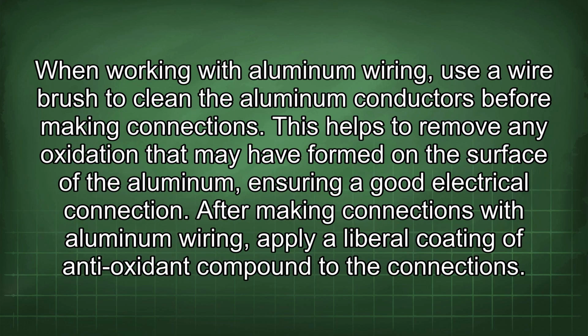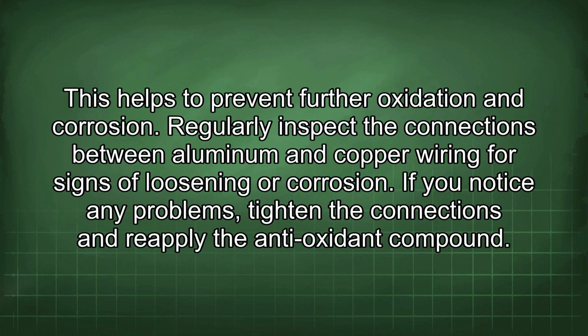When working with aluminum wiring, use a wire brush to clean the aluminum conductors before making connections. This helps to remove any oxidation that may have formed on the surface of the aluminum, ensuring a good electrical connection. After making connections with aluminum wiring, apply a liberal coating of antioxidant compound to the connections. This helps to prevent further oxidation and corrosion.